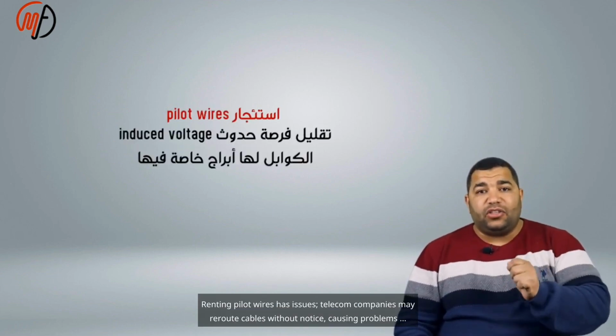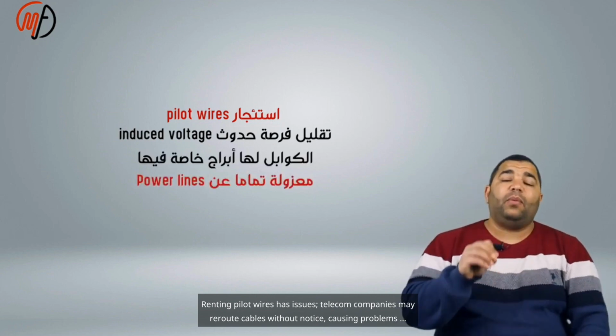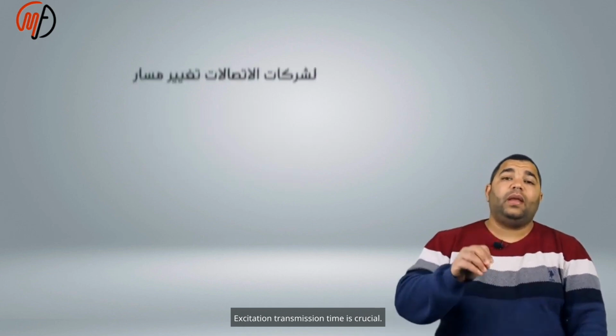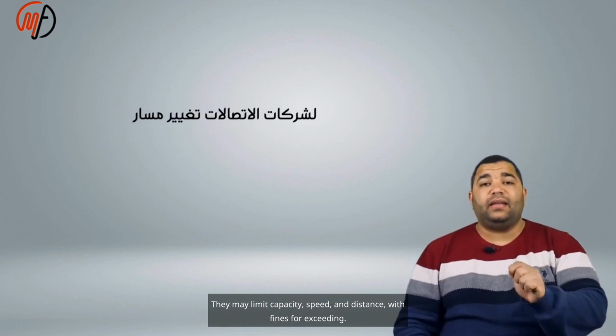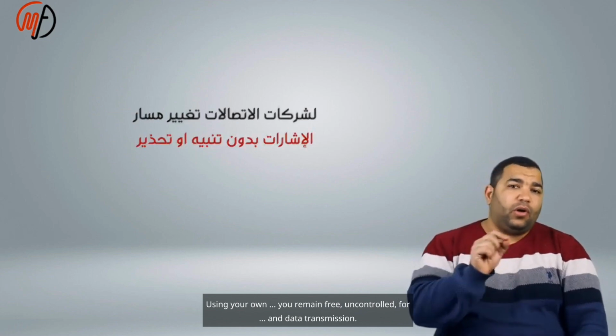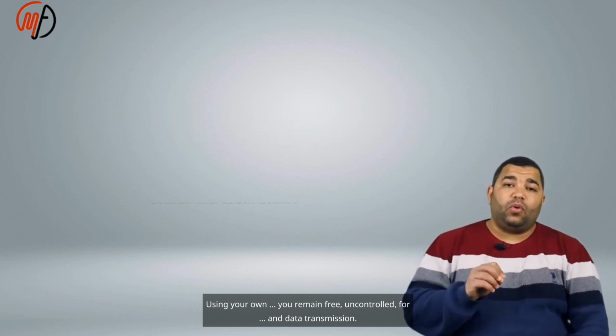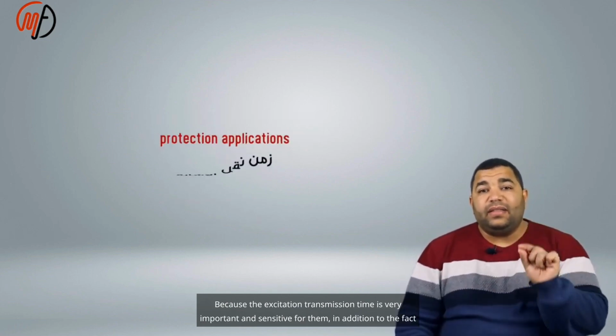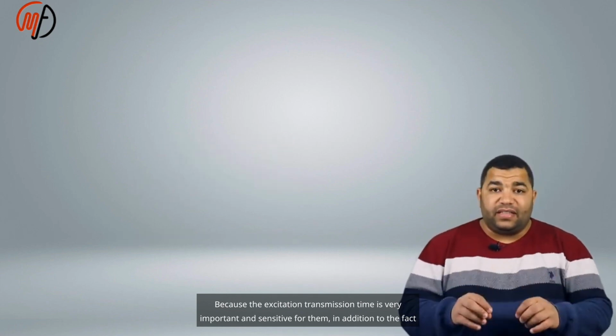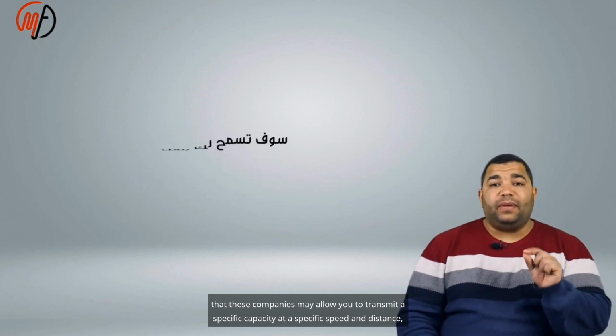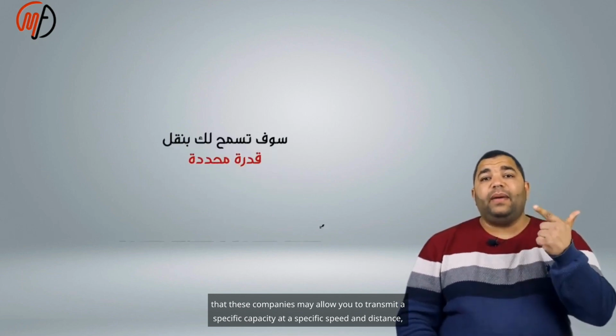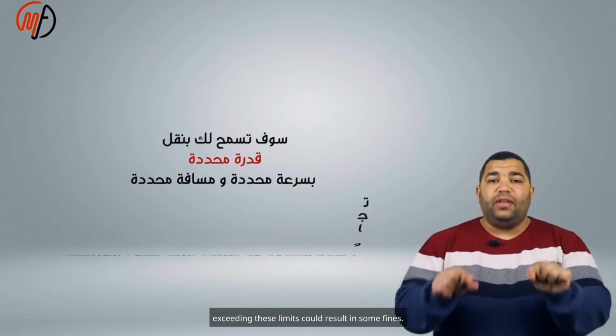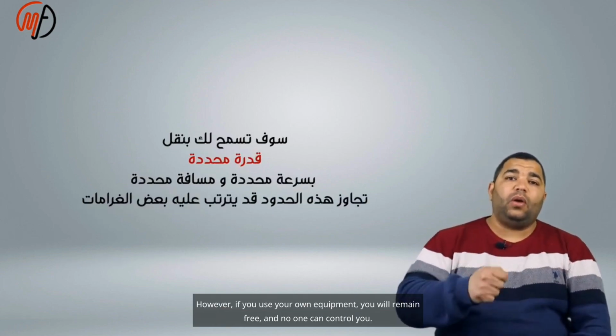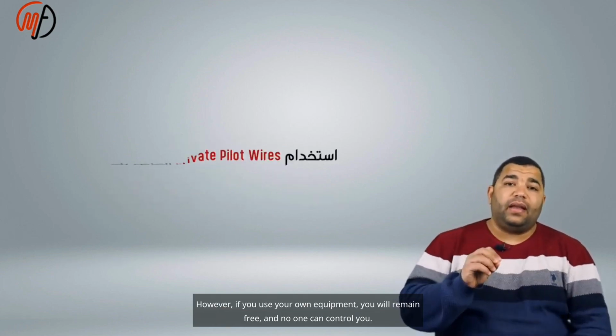Renting pilot wires has issues. Telecom companies may reroute cables without notice, causing problems. The excitation transmission time is crucial and very sensitive for protection. They may limit capacity, speed, and distance, with fines for exceeding these limits. If you use your own equipment, you remain free and no one can control you.